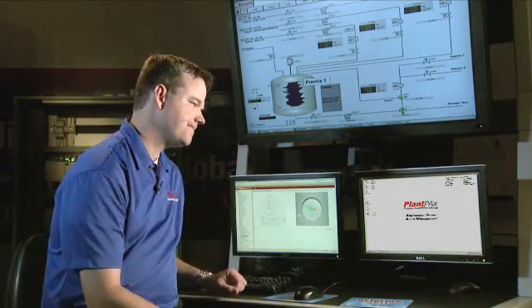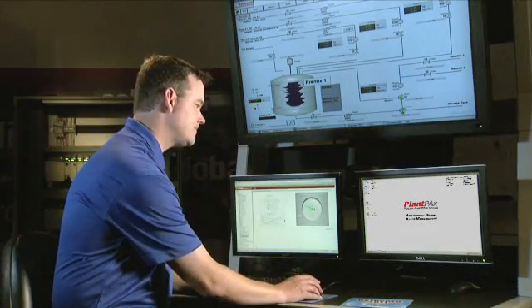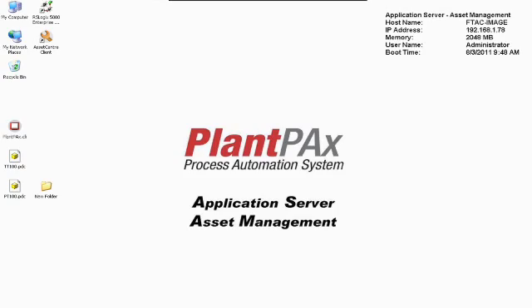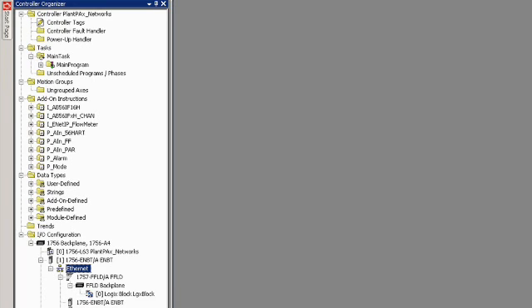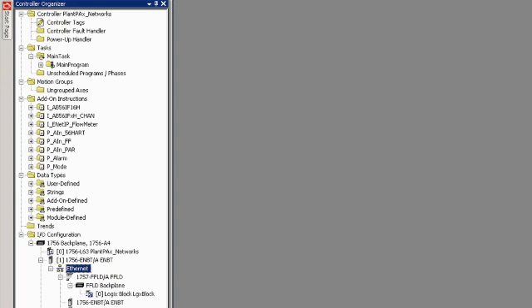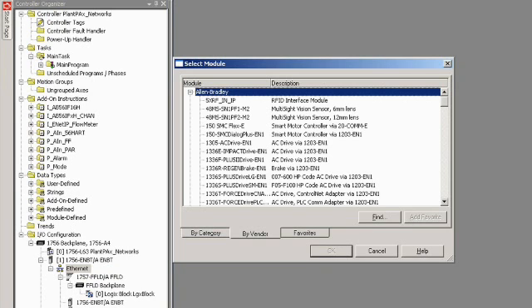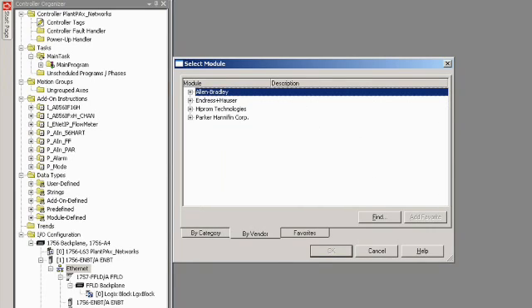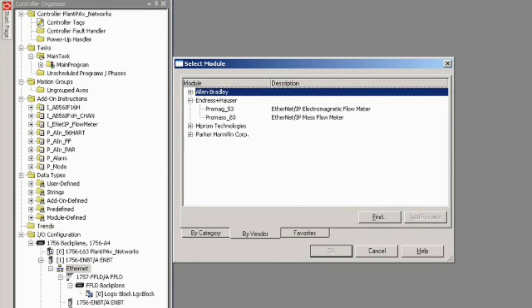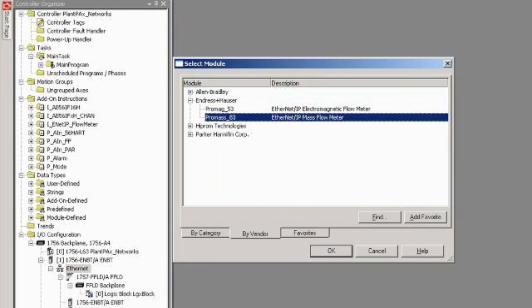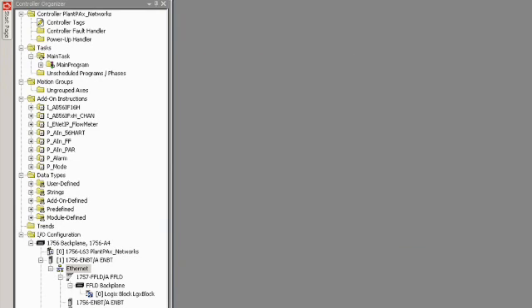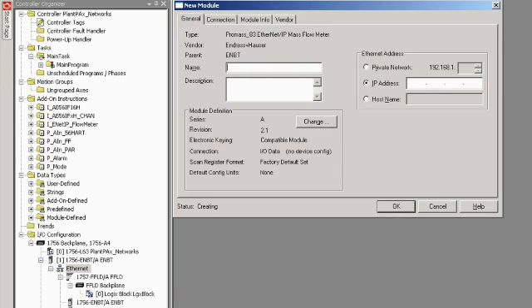Now let's get started. We can now open the Logix 5000 window, where we can right-click on Ethernet and select New Module. We have the option to search by vendor, where we'll select Endress+Hauser. We'll choose the device we want. I have a Promass 83 device for this demo, so I'll select that, and then we'll hit OK.